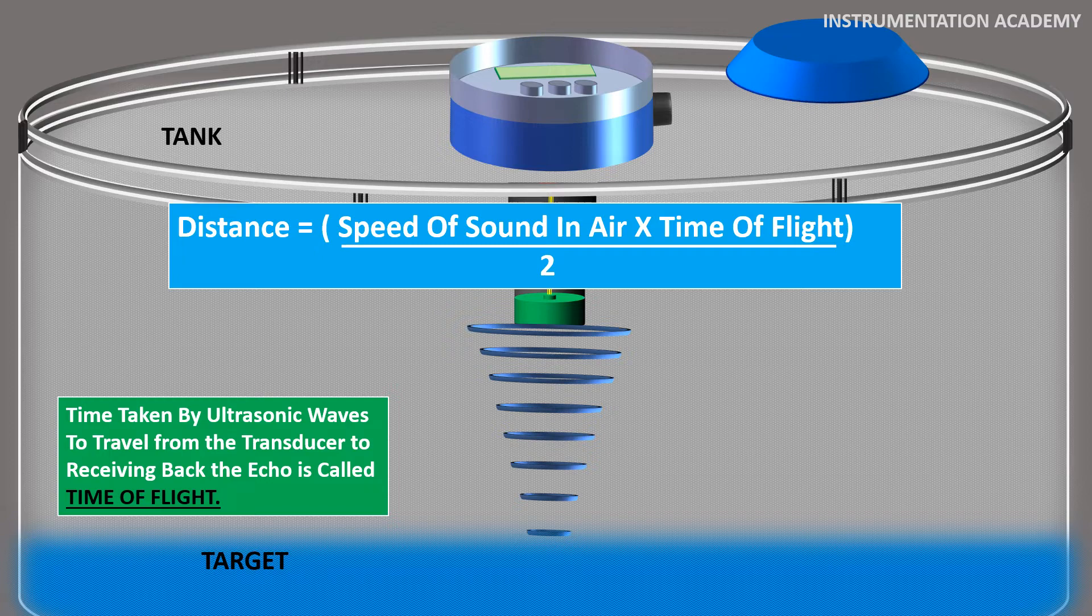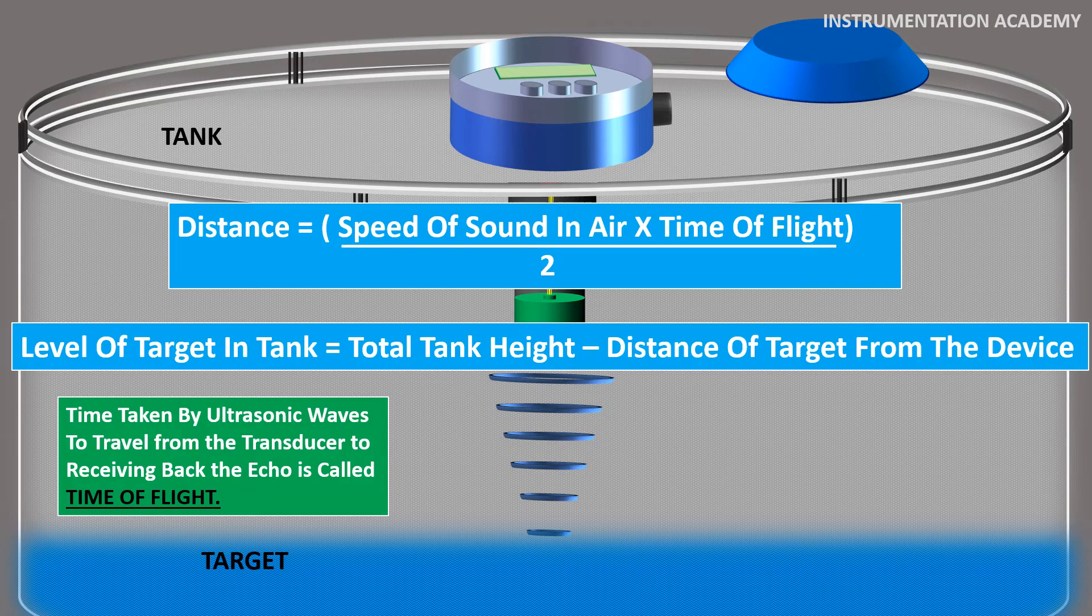Once the transmitter is programmed with the height of the tank, the level of target in the tank is calculated by the microprocessor using the formula: Level of target = Total tank height - Distance of target from the device.